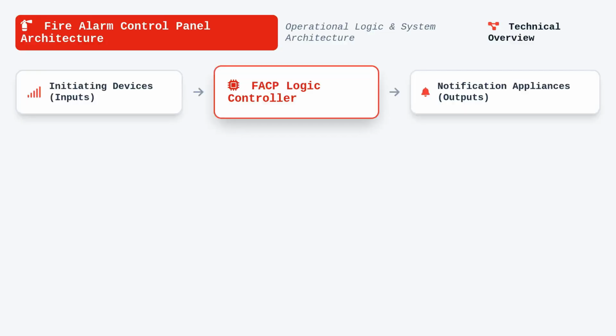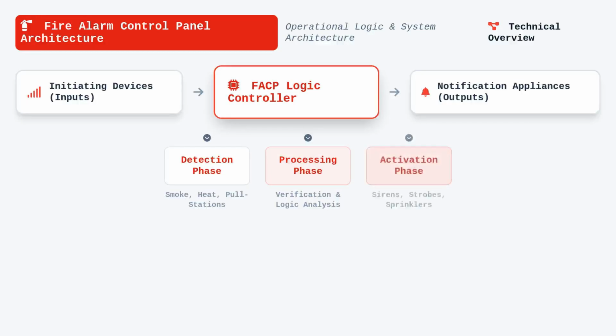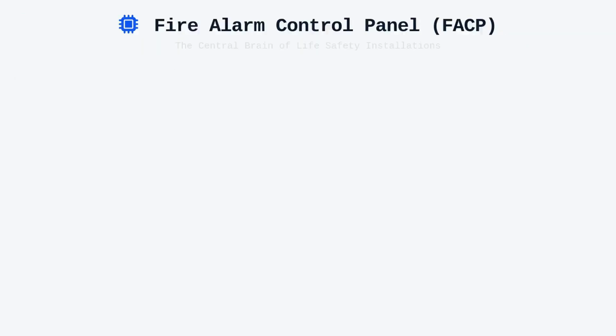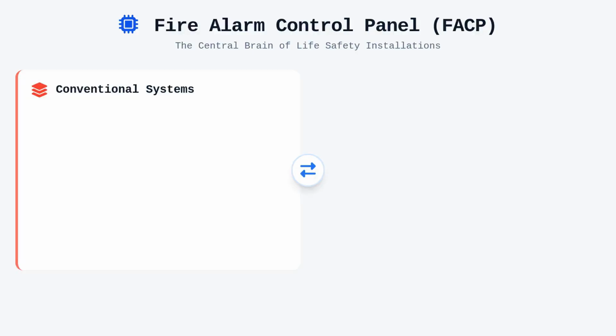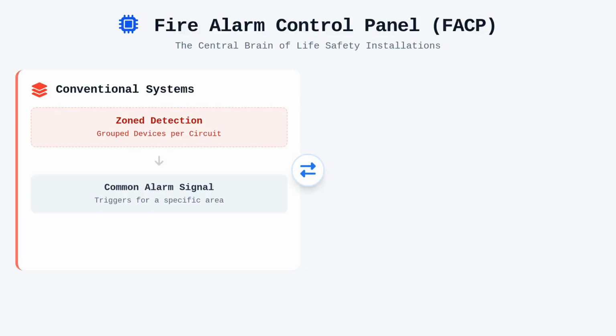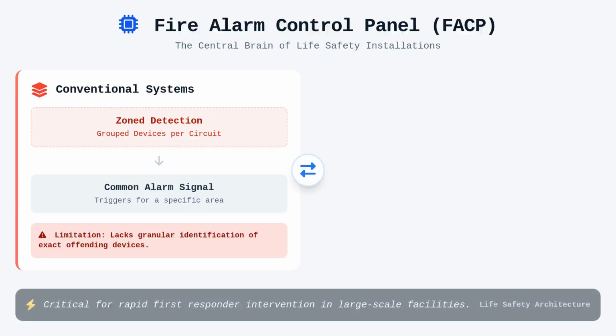Welcome back, everyone. Today, we are delving into the architecture and operational logic of fire alarm control units. The Fire Alarm Control Unit, or FACP, acts as the central brain of any life safety installation, coordinating inputs from initiation devices and dispatching signals to notification appliances. In conventional systems, the architecture relies on zone detection, where a circuit is populated with devices that trigger a common alarm for a specific area, lacking granular identification of the exact offending device.